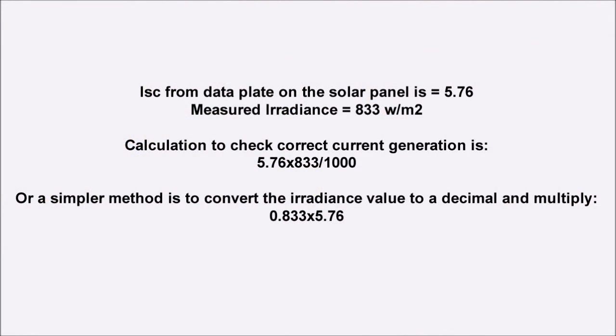The calculation you need to convert the values we've got to the actual current that we're going to expect would be to multiply the short circuit current value of the panel, which is 5.76, by 833 and divide the sum by 1,000. But to make life easier for myself, I just convert the 833 into 0.833. And if I multiply that by 5.76, I end up with 4.8 amps, which is approximately the value I'm expecting to get.